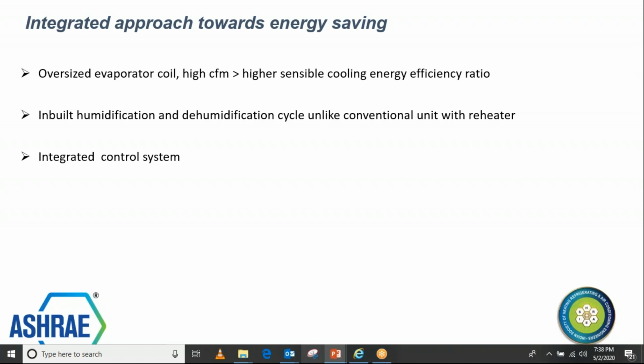The reheater will obviously cool extra and then heat up the air, and will consume power on the heater side. Unlike in precision AC, it has its own intelligent control logic. This control logic will check the temperature and the room humidity, because all the dehumidification, humidification and heating are built into the unit. So overall, based on the complete demand of the room, it decides which component to run.